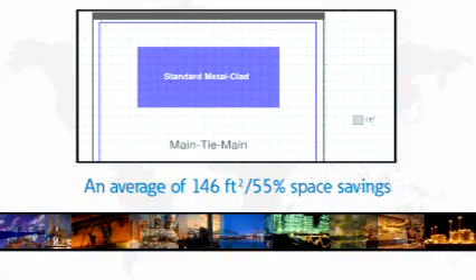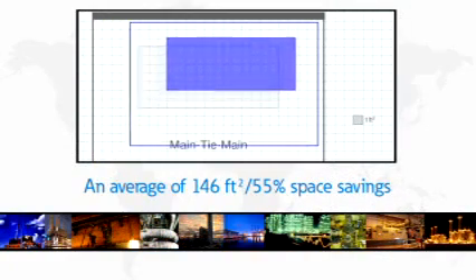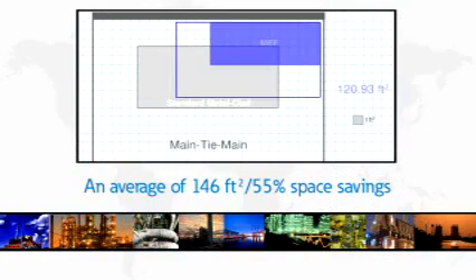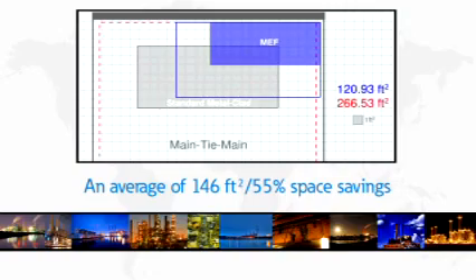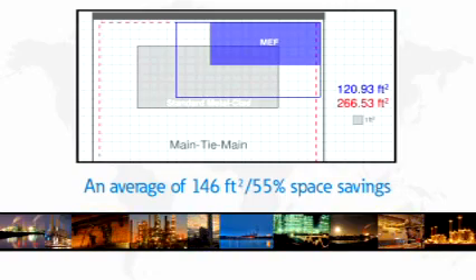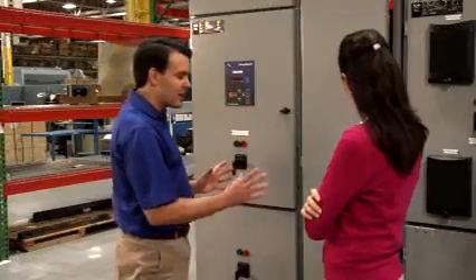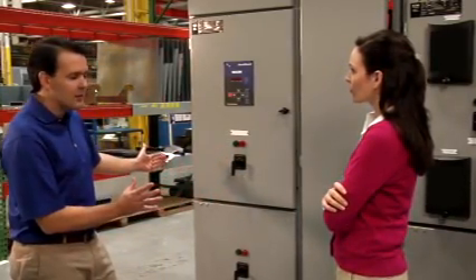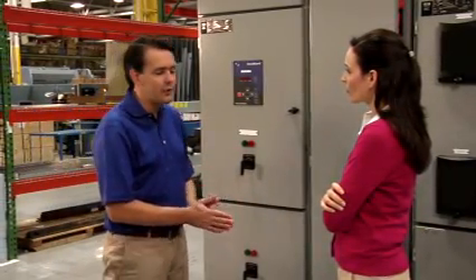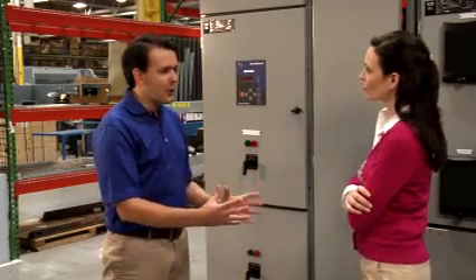So now we can slide this against the wall to the side and slide it against the wall in the rear and actually have this positioned in a corner, eliminating an aisle all the way around the switchgear, which would be needed if you had to get access. And now we've eliminated 2 aisles, plus the overall depth of the switchgear is only 60 inches deep. So we've, again, very small footprint.